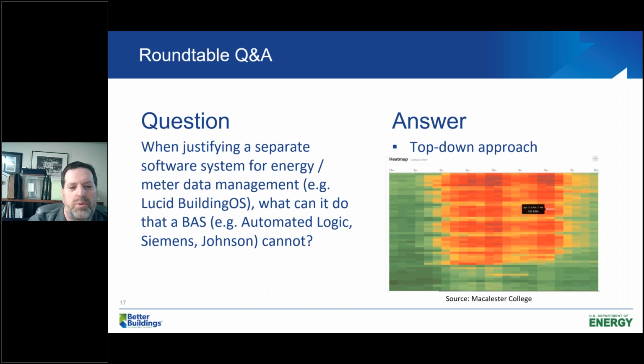On the previous slide, you mentioned specific faults. It doesn't tell you the simultaneous heating and cooling, but it can tell you start-stop schedules and high base loads, things like that. So you can set up trends in the BAS, though, to potentially do some of these things as well, but the EIS will tell you more analytics around it. The BAS is really designed to provide control of the equipment. So it gets data, and then it tells it to start, stop, to increase temperature. There are alarms in the BAS. If temperatures get too low, like freeze stats or filter alarms. But it doesn't run analytics to determine what occurred to create that condition.